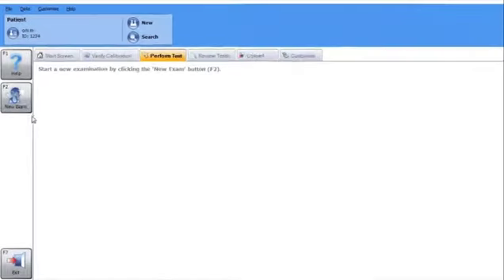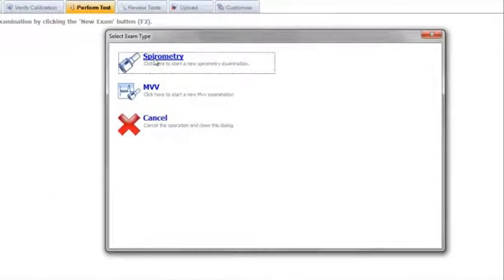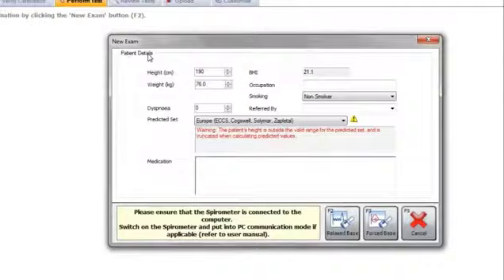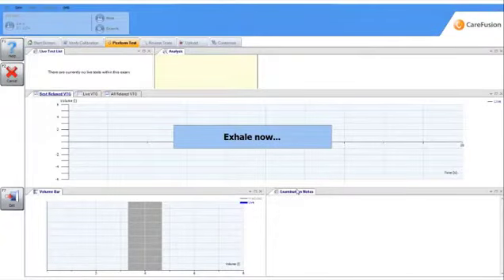To perform a relaxed spirometry test, select the tab Perform Test and click the button New Exam. In the dialog box, select the option Spirometry and then click on the button Relaxed Base.